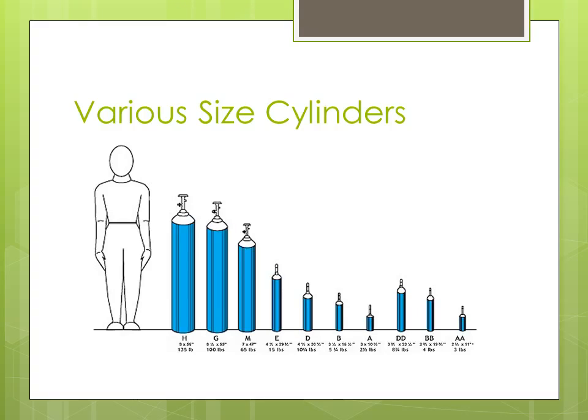Cylinders. Okay, well, when it comes to cylinders in healthcare, the two most common cylinders that you'll see are the H cylinder, and this is usually what you'll see brought in for bulk manifolds and for bulk systems. Typically, you might see this for nitrogen or nitrous, oxygen too. You might have this in a medical office building. You might also see that in a remote area that's not necessarily tied to the hospital. So it's pretty common to see the H tanks, and they're big.